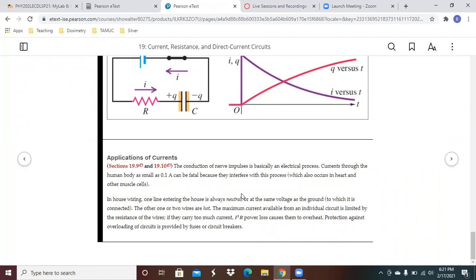House wiring: one line enters the house and is considered neutral, or at least at the same voltage as the ground. The other one or two wires are considered hot. The maximum current available from an individual circuit is limited by the resistance of the wires. If they carry too much current, the power loss is going to cause them to overheat. Protection against overloading the circuits is provided by fuses or circuit breakers.